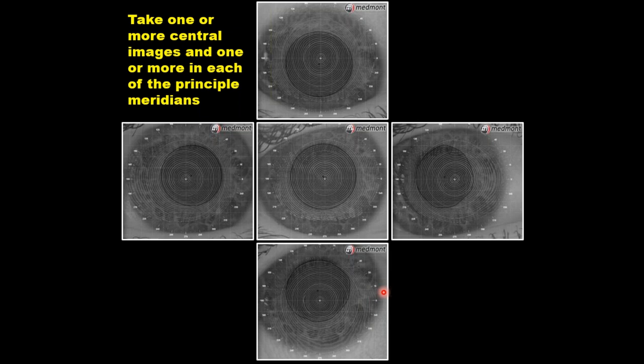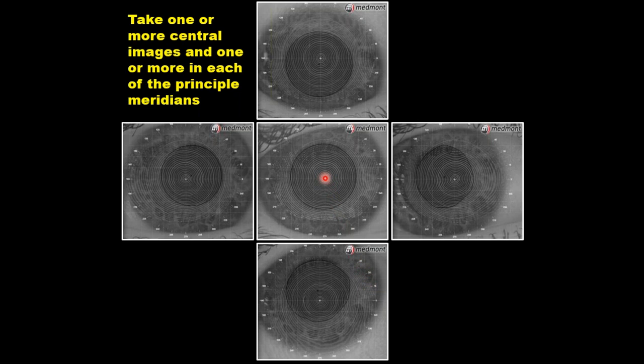To help us out, what Medmont does — and it's the only corneal topographer that does this — it allows us to take images with various fixations: with the patient looking right down the center, looking up pushing the rings down, looking nasal pushing the rings temporal, and looking temporal pushing the rings nasal. Essentially we're moving the Placido reflection all over the cornea.